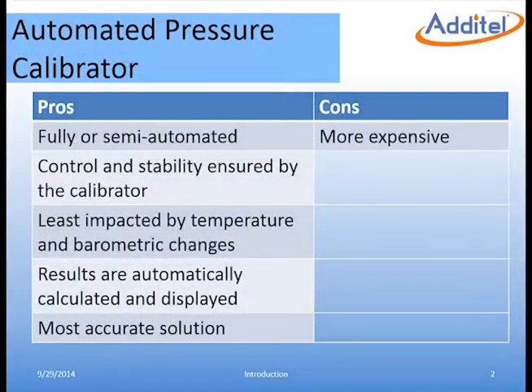Although the equipment used is more costly than the previous examples, this method can be fully or semi-automated depending on the DUT. Measurements are controlled and stability is ensured by the calibrator. The 761 is much less influenced by environmental changes than the previous example and the results are automatically displayed and calculated.